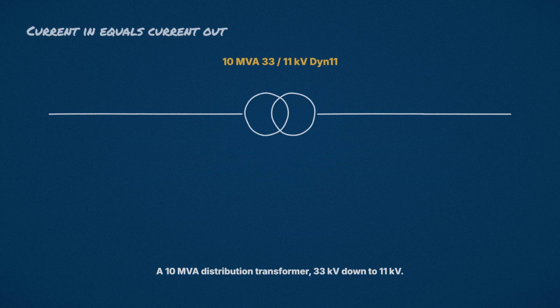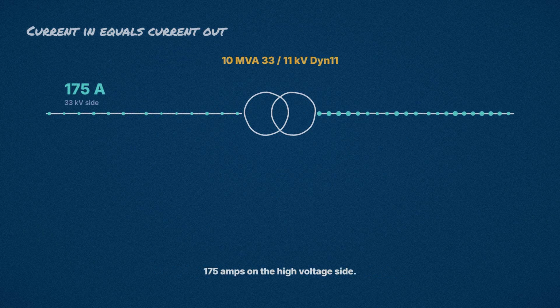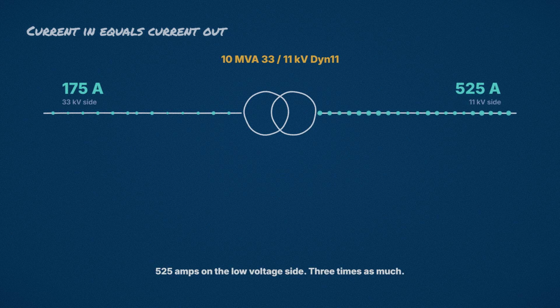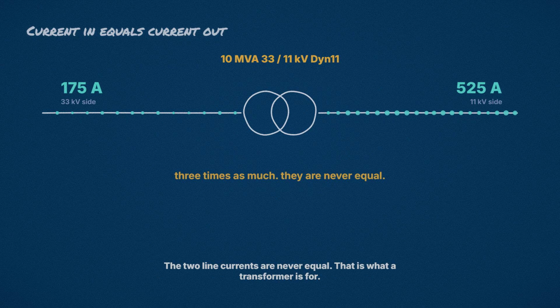Now look at what we are protecting. A 10 megavolt ampere distribution transformer, 33 kilovolts down to 11. At full load, it draws 175 amps on the high voltage side and 525 amps on the low voltage side, 3 times as much. So the two line currents are not equal, and they never will be. That is what a transformer is for. What balances is the power, and the ampere turns in the core. So we pick the current transformer ratios in that same 3:1.